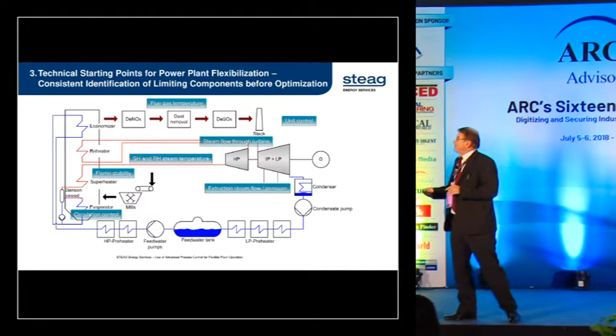In this screen, this area is shown. We have to consider circulation, especially for once-through boilers, and circulation control. We have to look especially at flame stability and flue gas temperatures. In all power plants we have DeNOx devices and FGDs; DeNOx especially requires a pretty small temperature window. If we go down in load and the temperature goes below a specific point, we'll have problems with air preheaters.